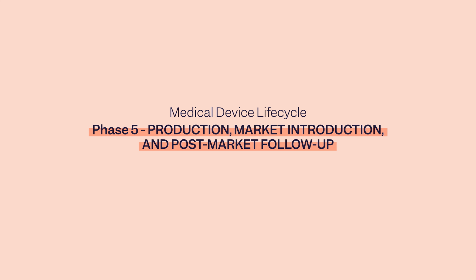If you plan to market your products in the EU or get certified according to the EU MDR, then you should register with an EU database known as the EUDAMED system. Once the medical device and the QMS are certified by a notified body, the device is ready to market.